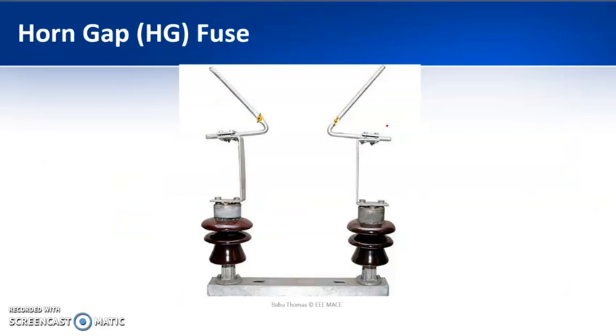So HG fuse is nothing but this, which looks like horns, and that is why it is known as a horn gap. And you need to also have a fuse element. The fuse element will be very thin in nature. It will be just inserted between these 2 terminals, and the fuse element will be very small because at 11 kV, at high voltages, the current will be very small, very little current will be passing through the system. So under any kind of fault occurring in any of the systems, this fuse will blow off and thereby protect the system.